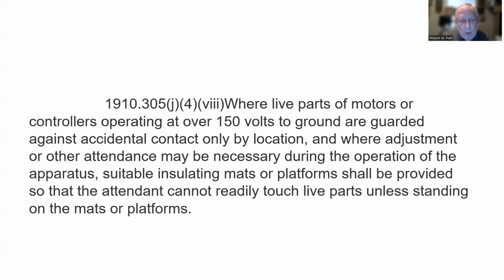Where live parts of motors or controllers operating at over 150 volts to ground are guarded against accidental contact only by location, and where adjustment or other attendance may be necessary during the operation of the apparatus, suitable insulating mats or platforms shall be provided so that the attendant cannot readily touch live parts unless standing on the mats or platforms.